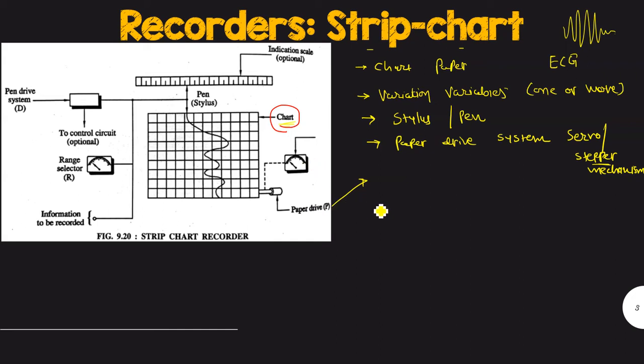Mostly the stepper mechanism is used for the purpose of paper drive. The speed of this chart or the drive is normally controlled by the speed selector. The speed selector is shown in this figure. The chart speed which is normally used inside of the strip chart recorder is in the range of 1 to 100 mm per second.